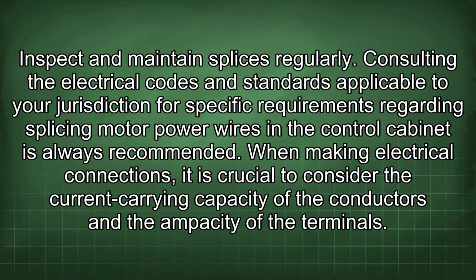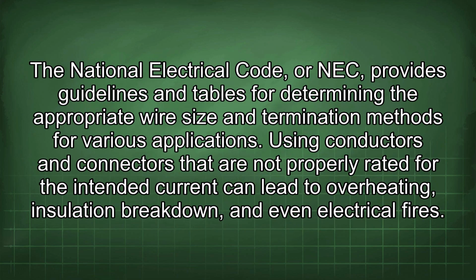When making electrical connections, it is crucial to consider the current carrying capacity of the conductors and the ampacity of the terminals. The National Electrical Code, or NEC, provides guidelines and tables for determining the appropriate wire size and termination methods for various applications. Using conductors and connectors that are not properly rated for the intended current can lead to overheating, insulation breakdown, and even electrical fires.